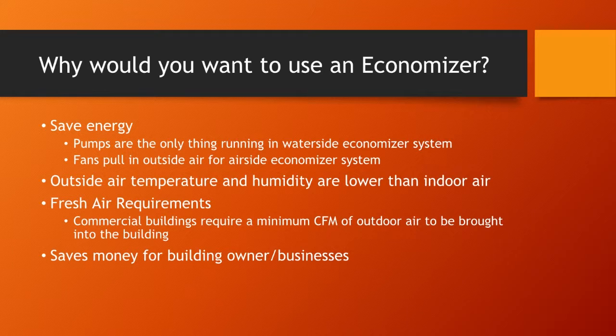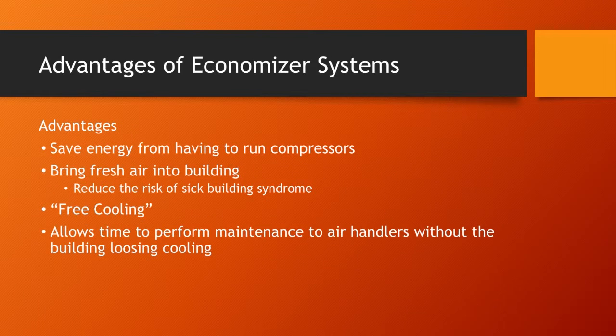So if you need to work on something on your air handler, if you're using strictly outdoor air, you can bypass some of the components on that air handling unit. Some of the advantages of economizer systems, number one, is save energy because you're not running compressors. Or in the case of a water side, you're not running compressors at full capacity. Either or, you're still saving energy.